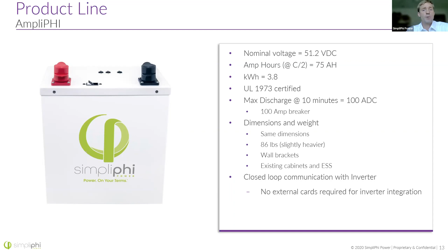Okay, so they are limited, and the limit on the number of these batteries that you can put in parallel is somewhere around 72 to 75 batteries. That has to do with the Cat5, Cat6 connections. The communication signal, you're going to daisy chain one battery to the next, to the next, to the next, to the inverter. And if you have too long of a chain of batteries, the communication signal gets too weak for the inverters to read, etc.